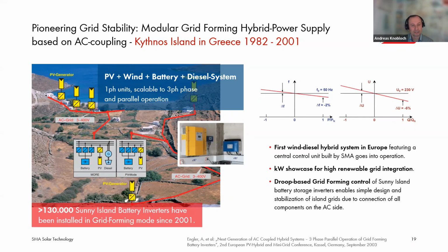There we provided on one side a central control unit that was built by SMA and also our Sunny Island inverters, the grid forming inverters that we put into operation in 2001, that allow a simple design and stabilization of island grids by connection of all components on the AC side. So it's an AC coupled battery storage system. These Sunny Island inverters are one-phase units, but they can be operated also in three-phase parallel operation. And using this droop control, that example has shown that kilowatt systems or island systems with very high renewable share were possible even 20 years ago. And since then, we have sold over 130,000 Sunny Island battery inverters that are installed and operate reliably all across the globe in island grids.